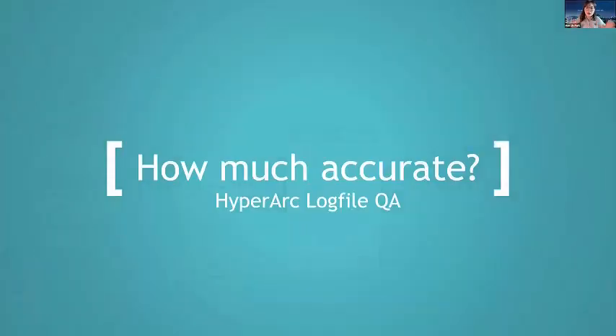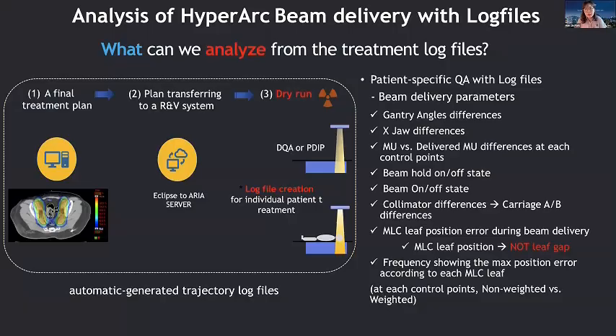Since most of the QA results were pretty good, we really wondered whether it was really accurate when HyperArc was delivered from the machine side. So I tried to dig into the log files. The log files are automatically generated by the machine after treatment. This log file consists of a whole bunch of data, such as the gantry angle, jaw, MLC, carriage differences, delivered MU values, and things like that.